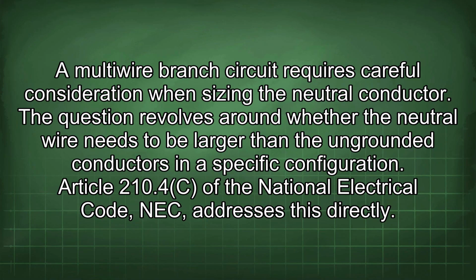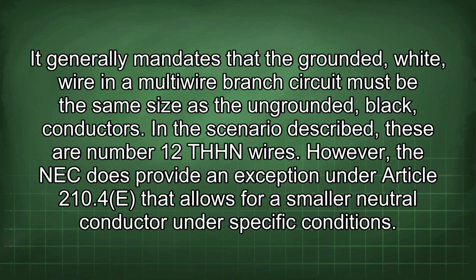A multi-wire branch circuit requires careful consideration when sizing the neutral conductor. The question revolves around whether the neutral wire needs to be larger than the ungrounded conductors in a specific configuration. Article 210.4(C) of the National Electrical Code, NEC, addresses this directly. It generally mandates that the grounded, white, wire in a multi-wire branch circuit must be the same size as the ungrounded, black, conductors. In the scenario described, these are number 12 THHN wires.